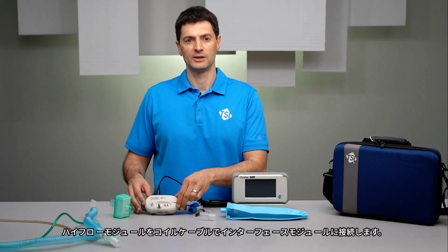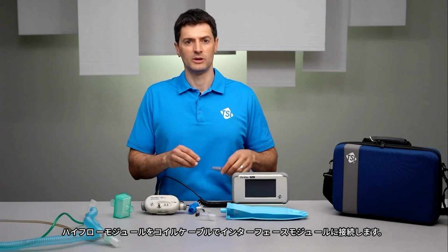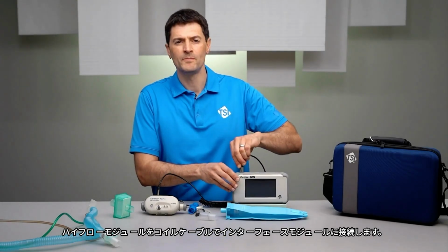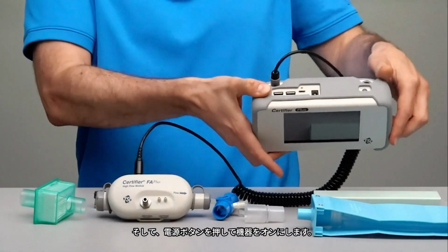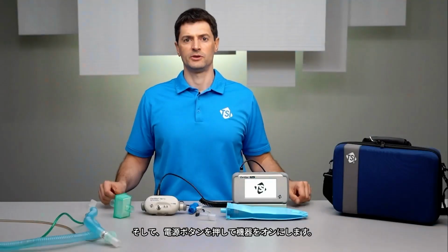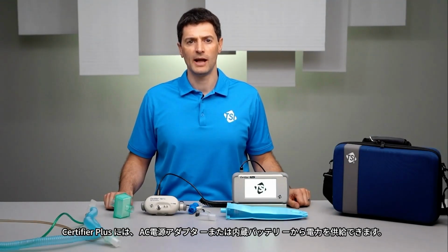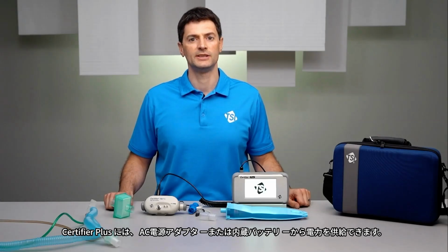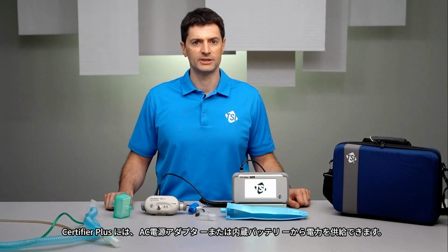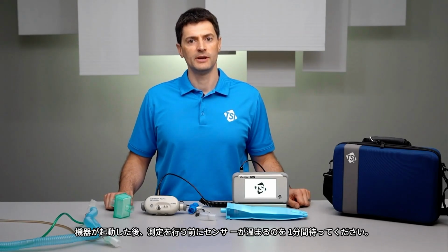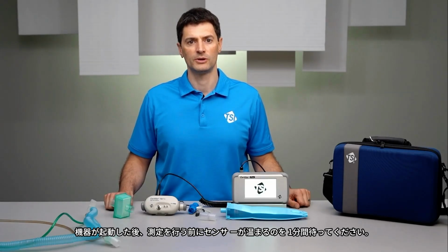Connect the high flow module to the interface module using the coiled cable, and then press the power button to turn the instrument on. Power can be supplied to the Certifier Plus using the AC power adapter or from its internal battery. After the instrument boots, wait 1 minute for the sensors to warm up before taking measurements.